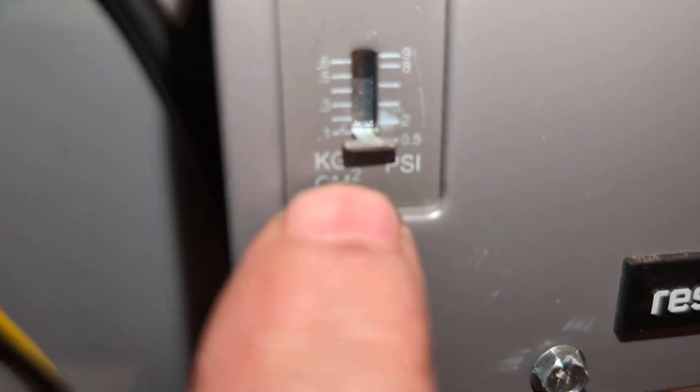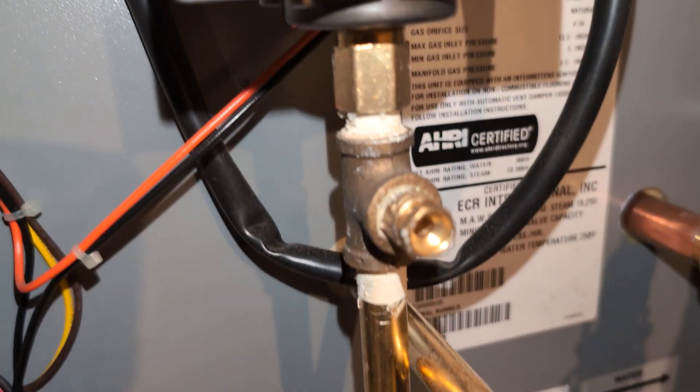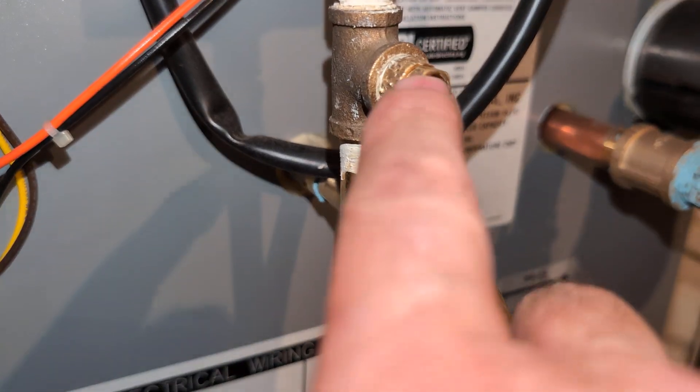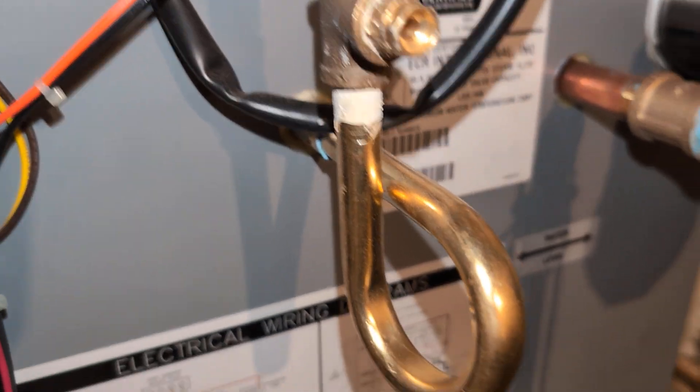We set the Pressuretrol to its minimum setting — a pound and a half max, half a pound on. And we have a T here so we can take this plug out and test to make sure the pigtail is clear.